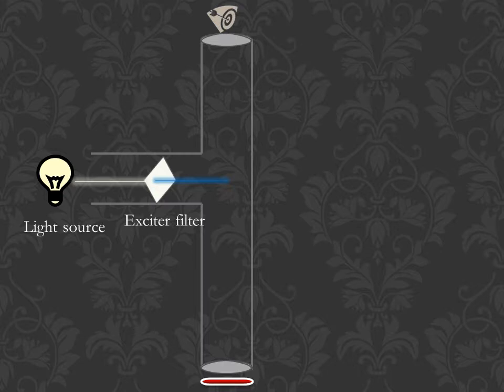So if this goes on this way, it is definitely not going to meet the specimen. That's why now we design a mirror, a reflector, so that the blue light is reflected onto the specimen coated with fluorescent substance. So there is a dichroic mirror. This mirror is not an ordinary mirror because this is a dichroic mirror.